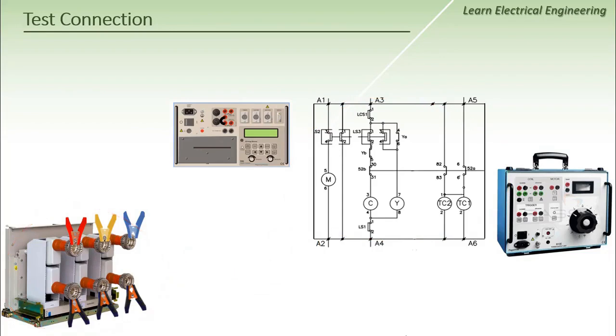All right, let's look at the first control circuit. The first thing in the control circuit is the DC control source. As for the DC control source, I can supply it from the DC control panel that is in the switchgear or GIS, and it is a 125 V DC control supply. Is it possible to use the same control supply voltage with the commands that I will give to the close coil and the tripping coil?